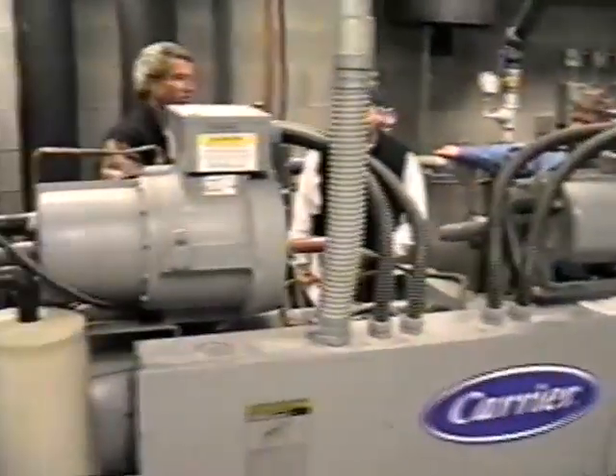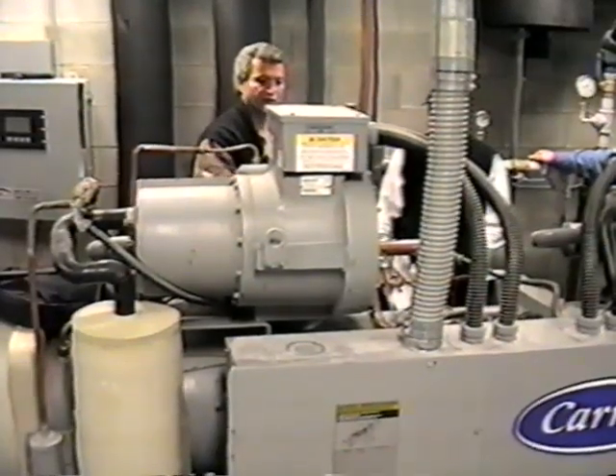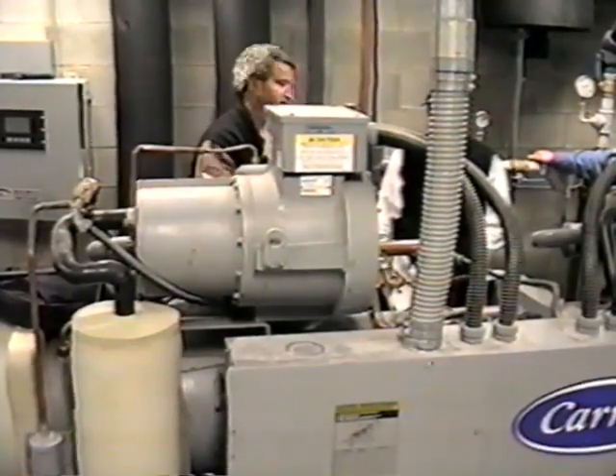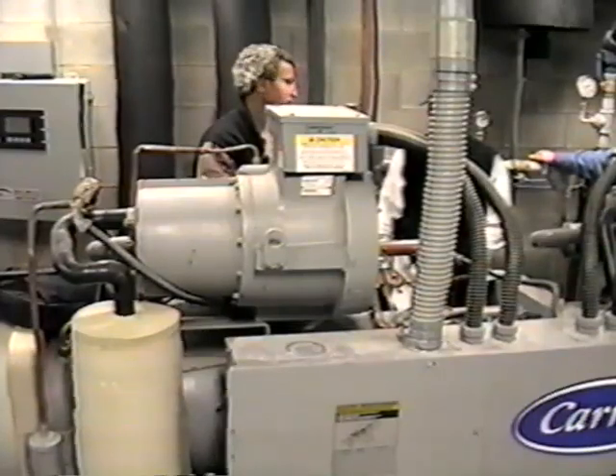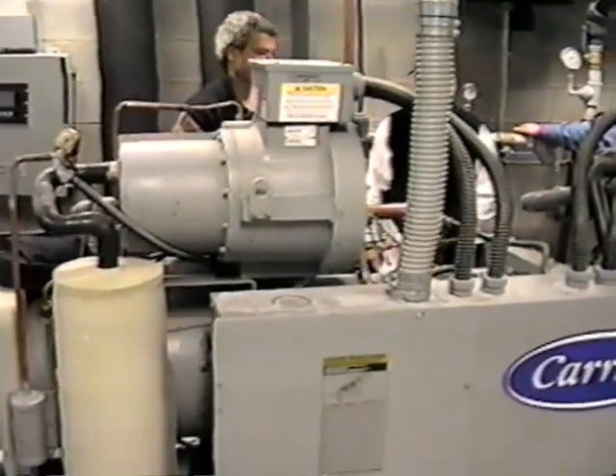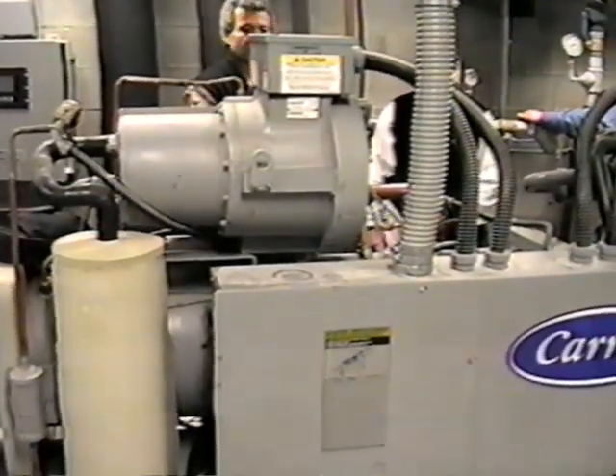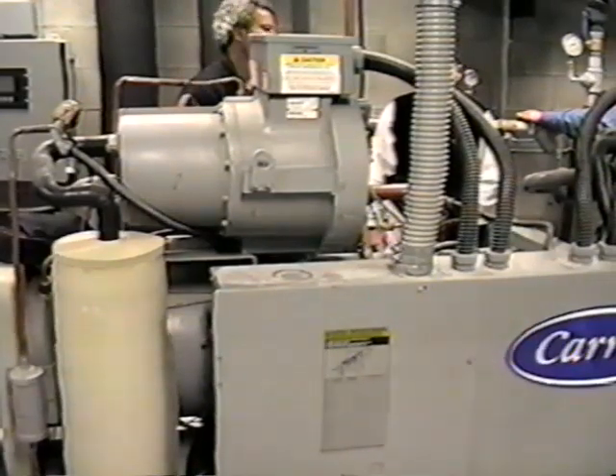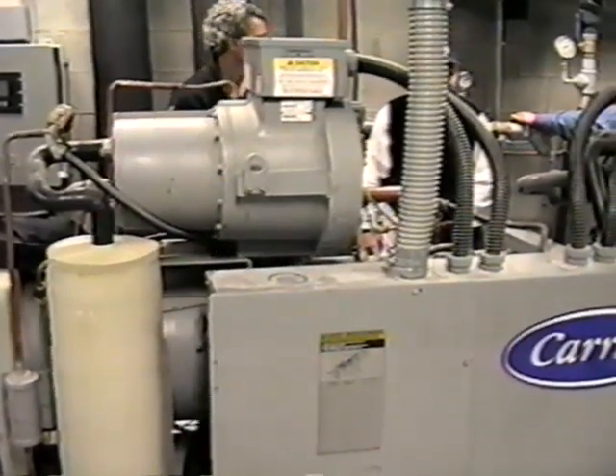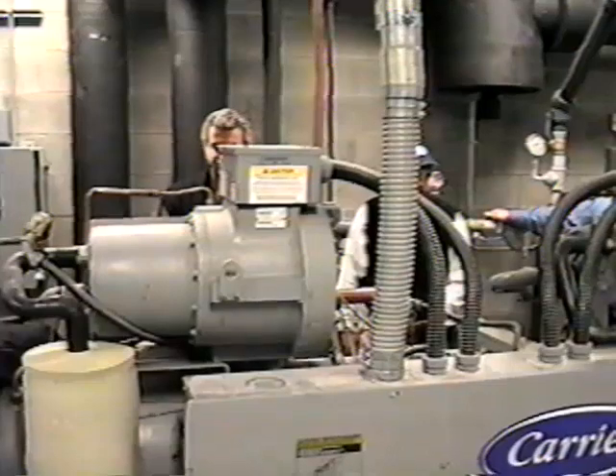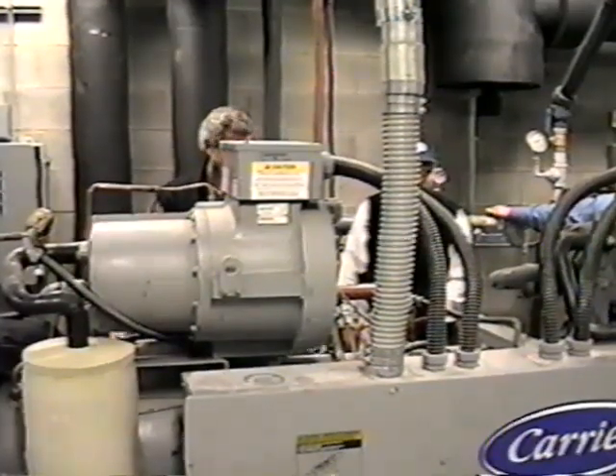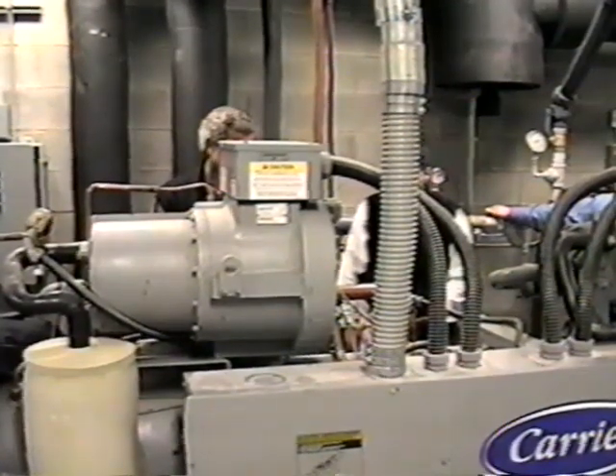These are your loading solenoids. They actually cover more or less of this. They pull a piston that covers more or less of the screw and gives you more capacity or less. So you'll hear those clicking on and off, and you'll hear the noise fluctuation as it loads and unloads. Other than that, that's pretty much it.